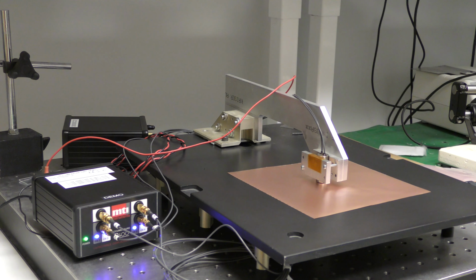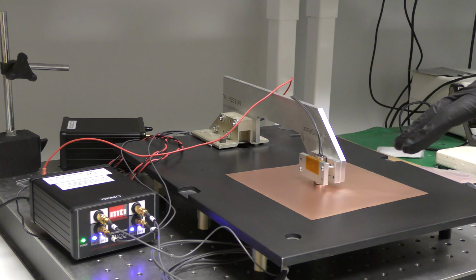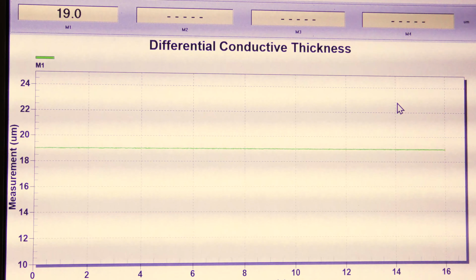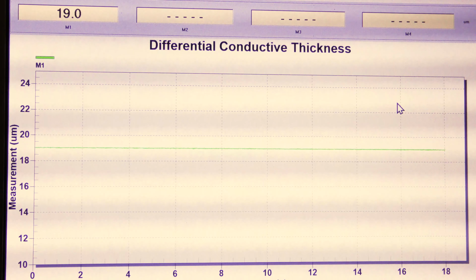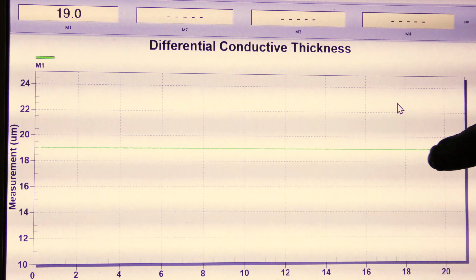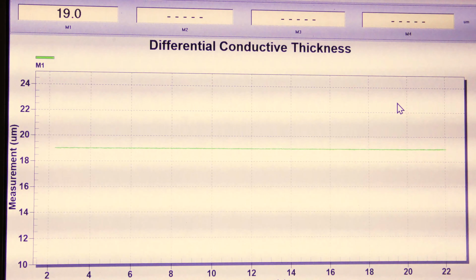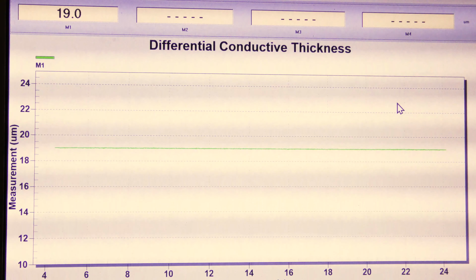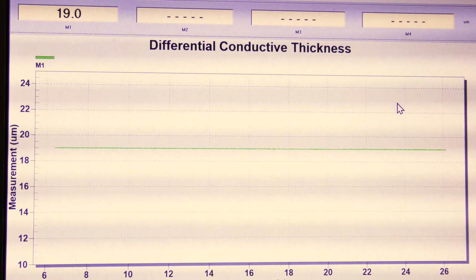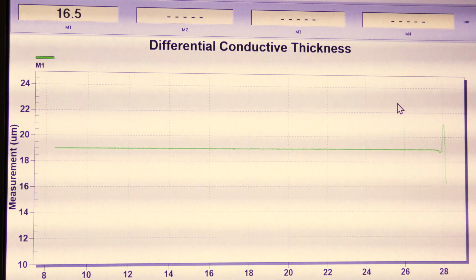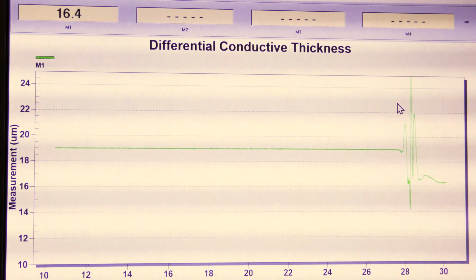We're looking at the center of the copper. We know it's 18 microns. Here we're reading 19, so it's 1 micron high. We're also running the monitor so you can see the thickness change. I'm going to slide the copper to the 12 o'clock position up near the top of the sample. See what we can see.